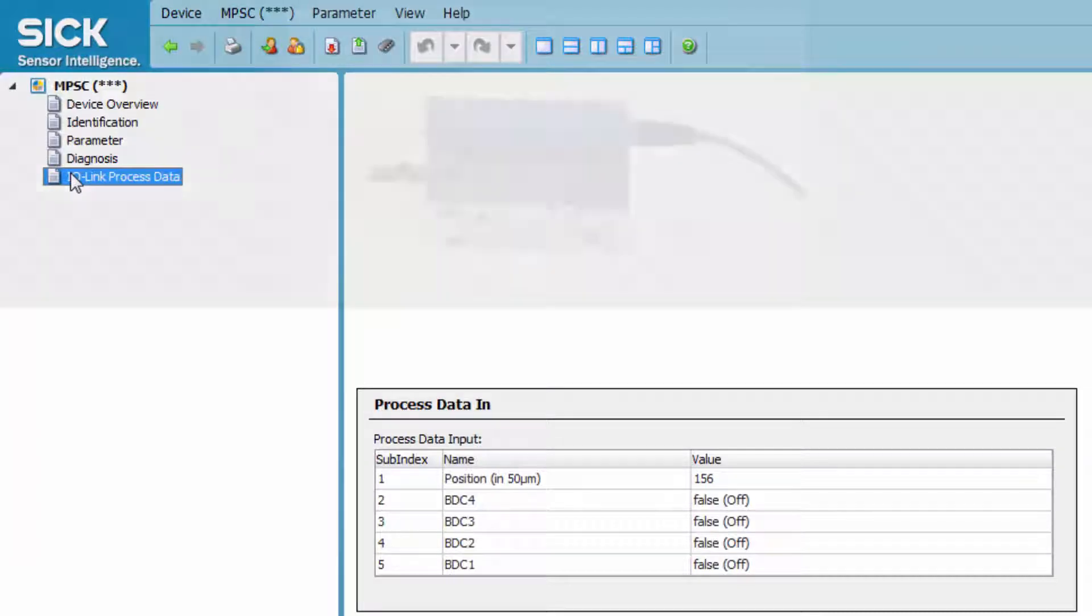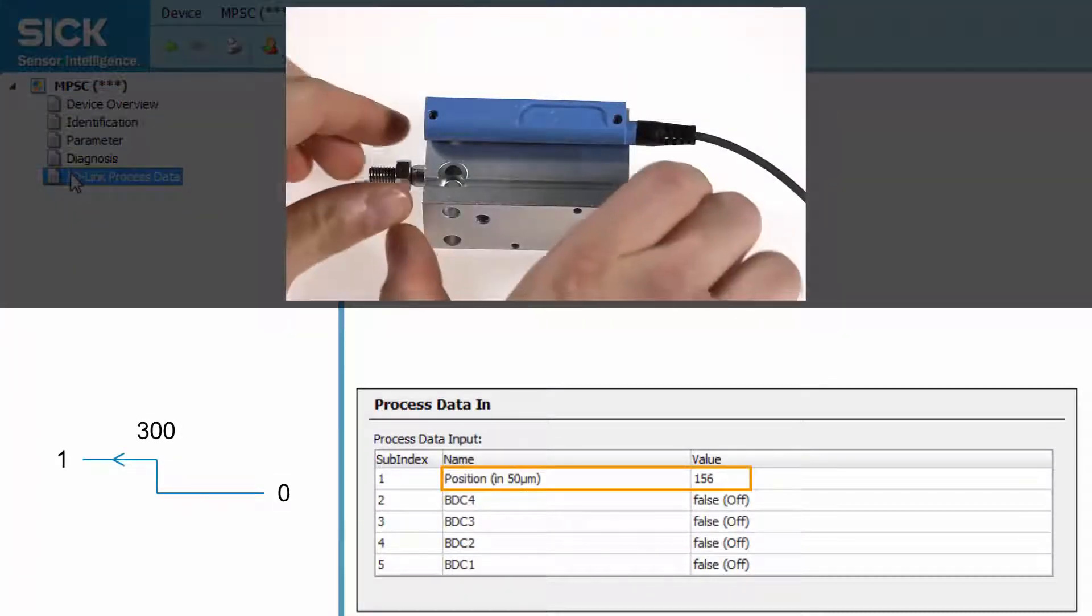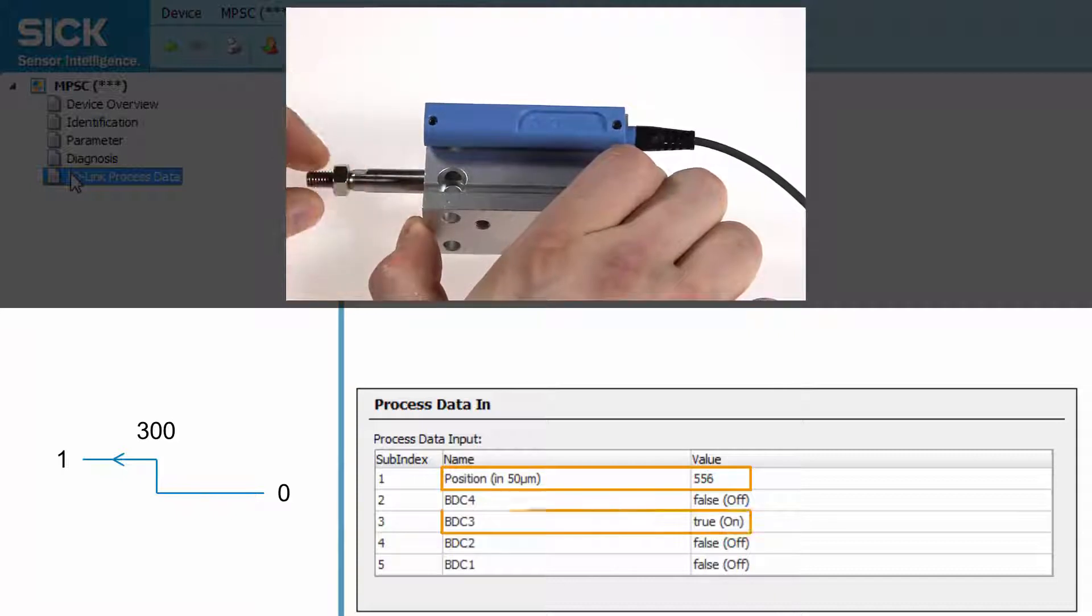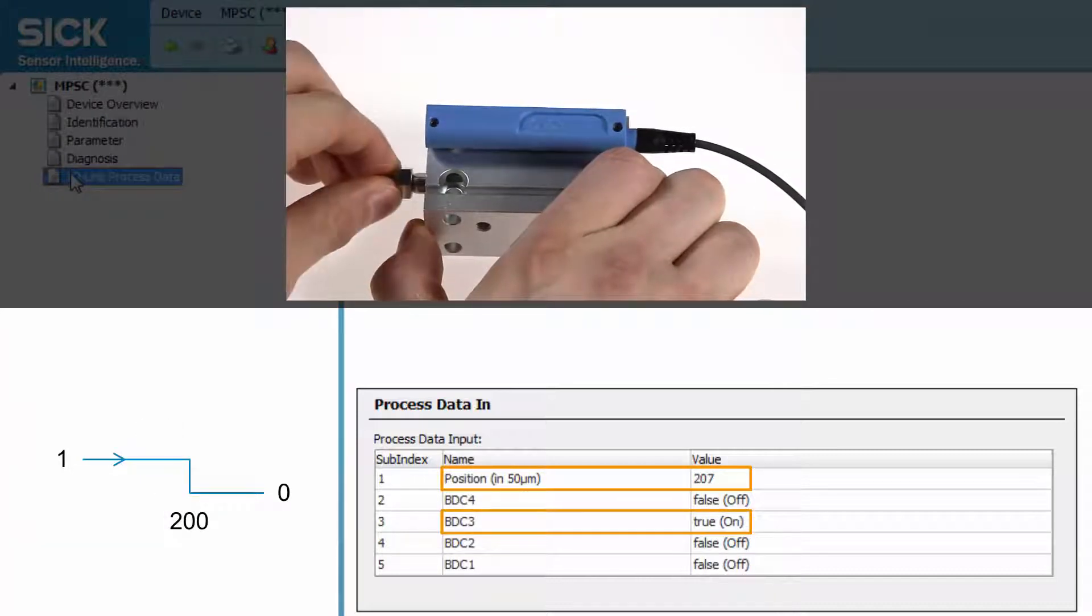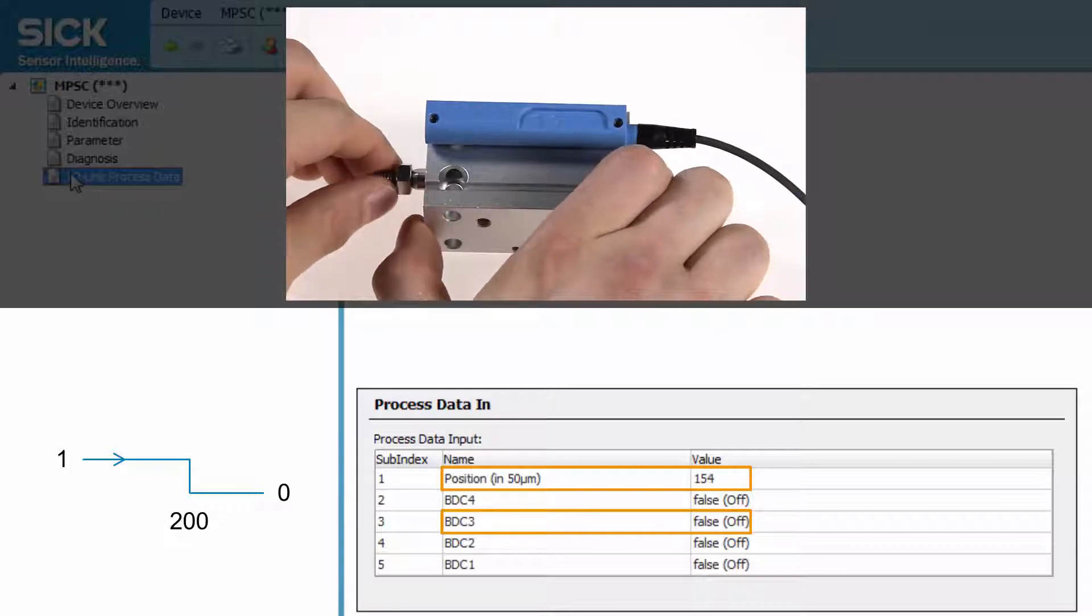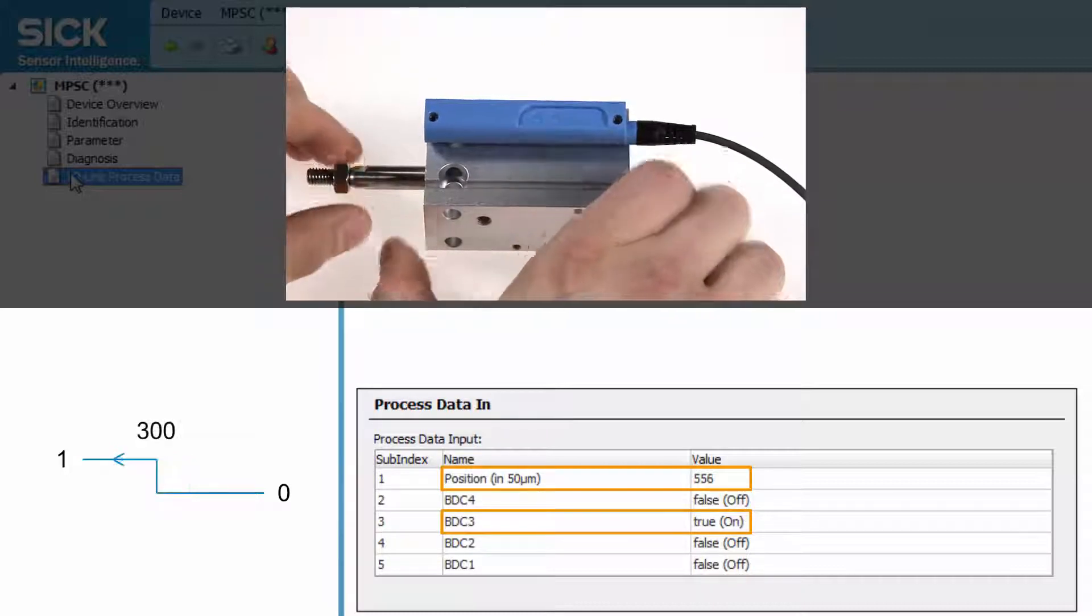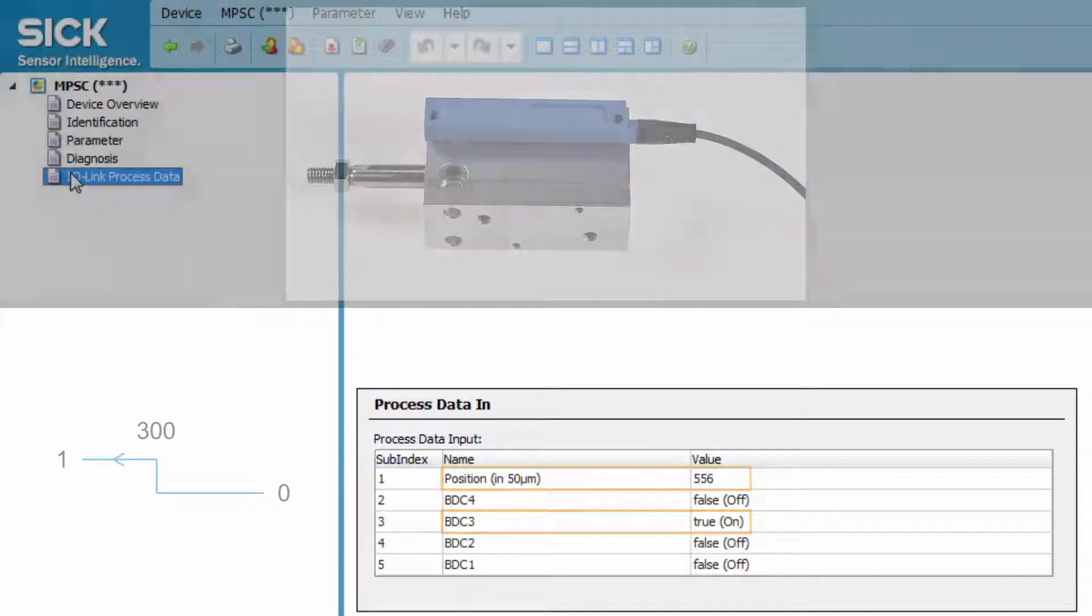The behavior of the output can be monitored by clicking on IO-Link process data and then observing the values of BDC3. As soon as the position is above 300, the value changes to true. It stays true until it falls below 200. The LED on the sensor represents BDC1, so no change for BDC3 is visible.